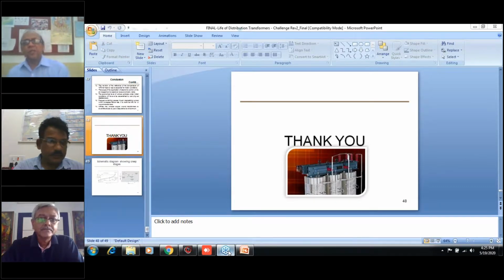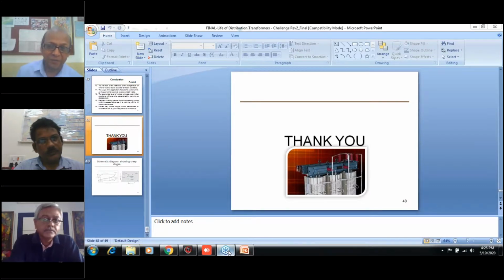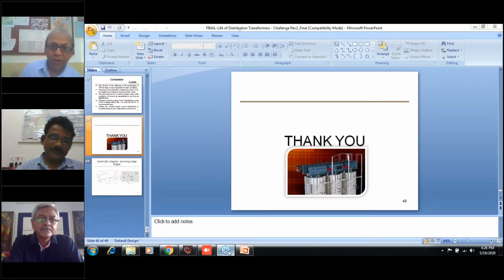See, you can have higher overloading designs, but for everything you have got a certain limit - you have to pay the cost for that. Proper supply, proper network is important. Once you ask for a different design, then I will ask, why not a higher rating? Question is, why not higher rating? Or if you have a specific problem, say a short-time problem - let us say you have a mixie in your house, it operates for half a minute or 1 minute, then it's switched off, isn't it? You can't have a transformer like that, operating for half an hour or 10 minutes, then switch off, then operate again. We can't do that. Therefore, we can definitely do certain things, no doubt, but not too many things - something, some minor.